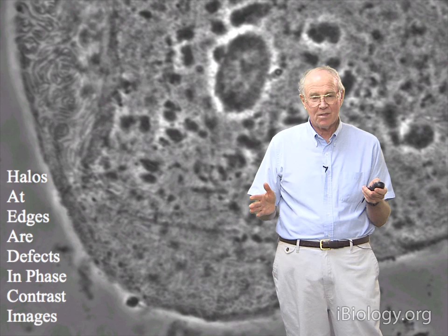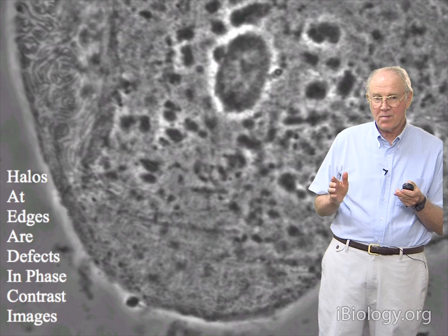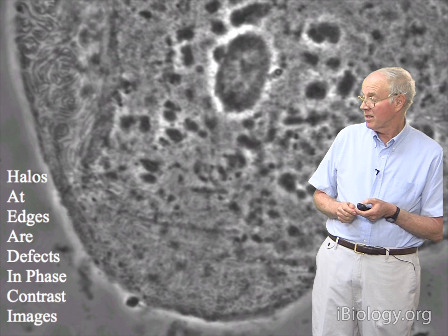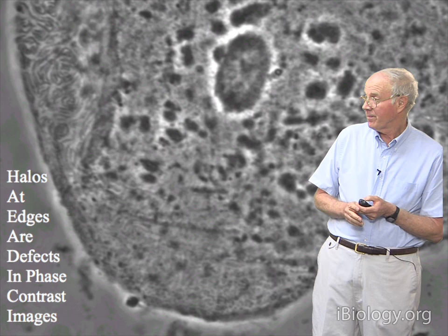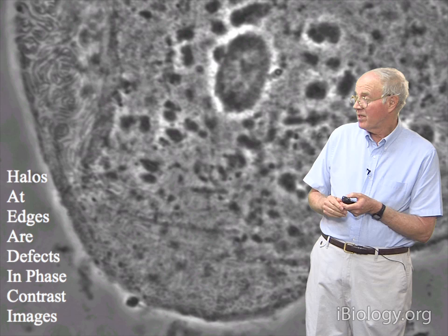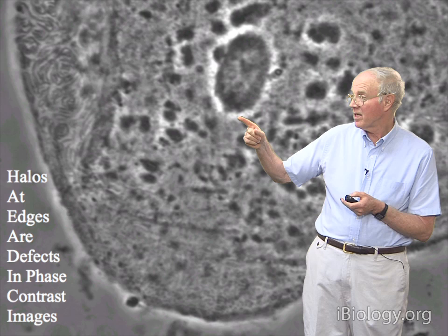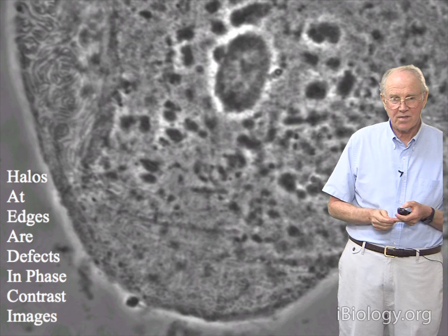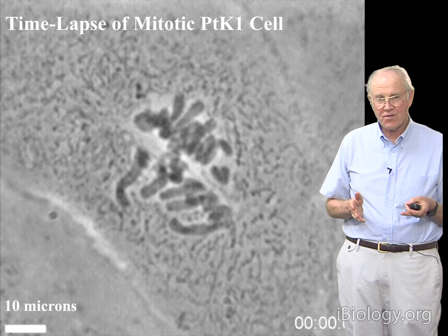Besides not being able to achieve the maximum resolution that the objective numerical aperture will allow, the other problem with phase contrast is that the phase ring is larger than the phase annular illumination. As a result, low-angle diffracted light — which contains information about low spatial frequencies in the specimen — is attenuated by the phase ring and doesn't get to the image plane. This produces halos around phase objects like the nucleus. In thicker specimens, those halos propagate up and down through the specimen and can cause confusion, much like in dark field.